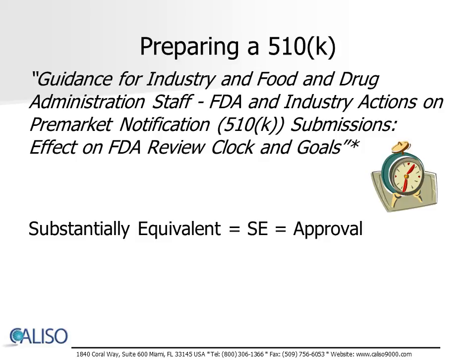If the submission has been found to be substantially equivalent, then an order declaring the device to be SE, or substantially equivalent, is issued to the 510(k) submitter, stating that the FDA has determined that the device described in the 510(k) submission is indeed substantially equivalent to a legally marketed device. An order declaring a device to be SE authorizes marketing of the device in the United States subject to specific statutory and regulatory requirements of the FDA.